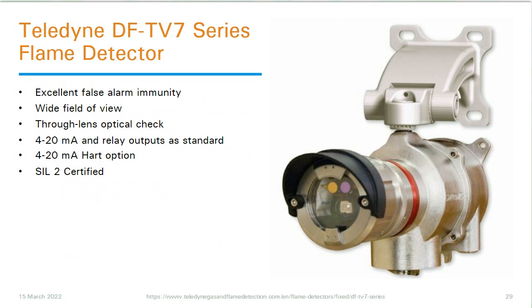Similar comments would apply to flame detection equipment, and this is the DF-TV7 series, which, amongst other things, has a very, very good immunity to false alarms. We mentioned earlier on that too many alarms can distract operators. If an alarm is repeatedly a false alarm, then people become a little bit immune to it. So a flame detector that's not being activated by sunlight or some other false alarms is increasingly valuable.